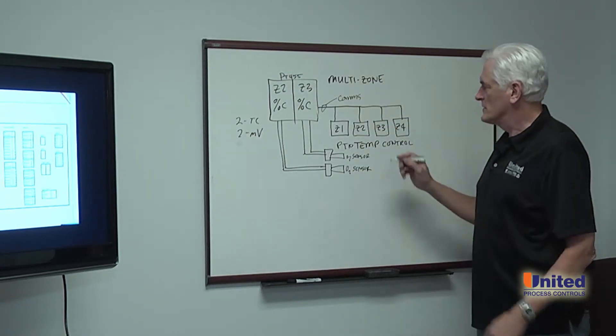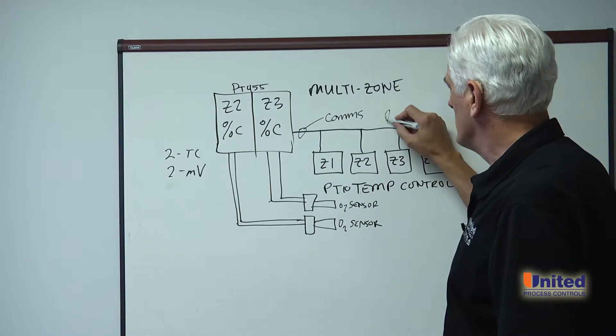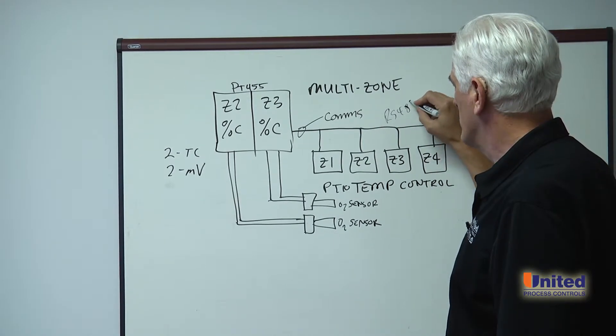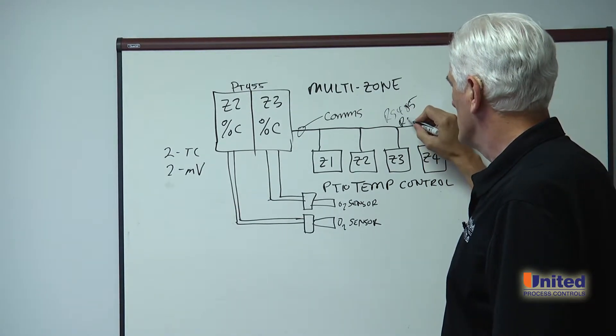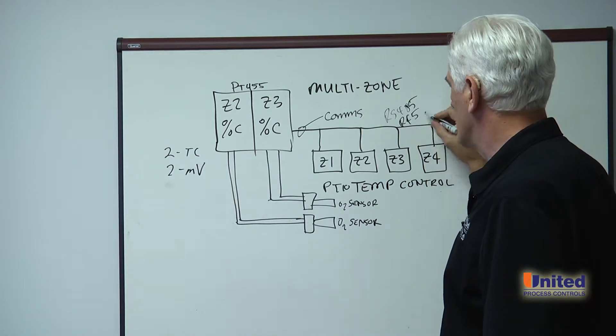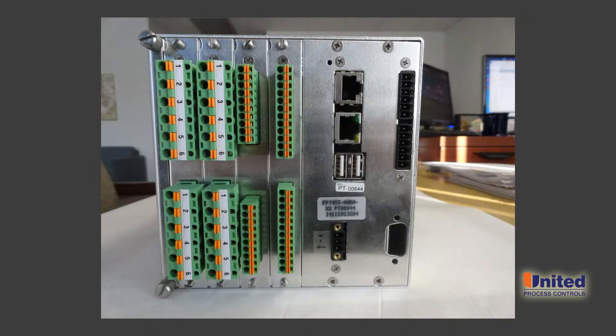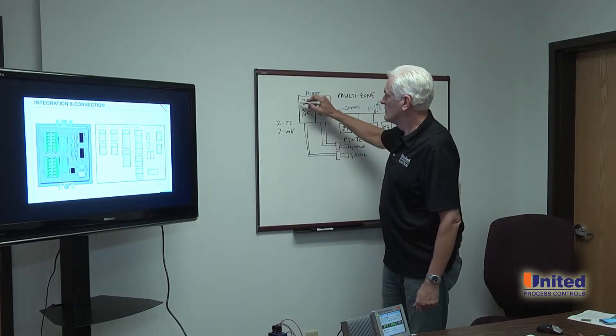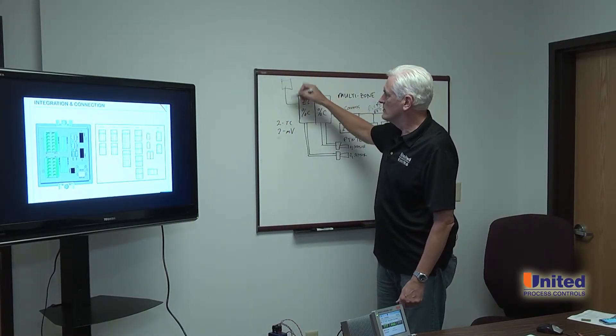Temperature control is going to be managed by external slaves, which can be configured in the instrument. The slaves can communicate on either the RS-485 port or the RJ45 Ethernet jack. Either one of these COM ports on the back of the instrument can be used, or either one of the Ethernet ports. Typically you have one Ethernet connected to a SCADA system going out to the computer.